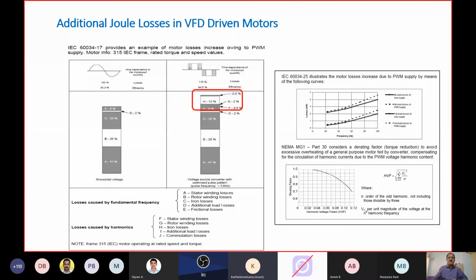Now, this is a slide from IEC 60034-17. Part 17 deals with the inherent losses within the motor. What you see on the left-hand side here, I don't know if my cursor is visible to you, if it is, you will notice that there are 4 losses: iron, friction, stator copper losses, rotor copper losses, and the stray losses. Whereas when you apply the motor with a VFD, you will find that additional losses are there within the motor. So with the VFD, the motor's own losses will increase, and therefore the efficiency will come down.